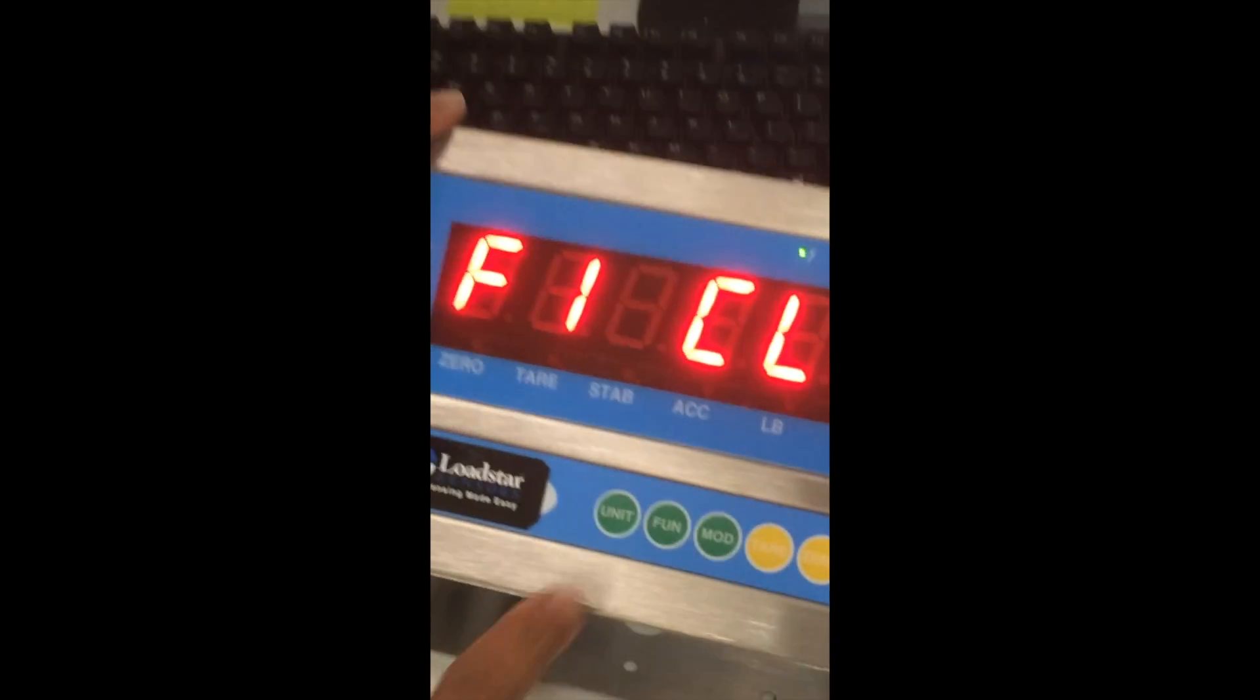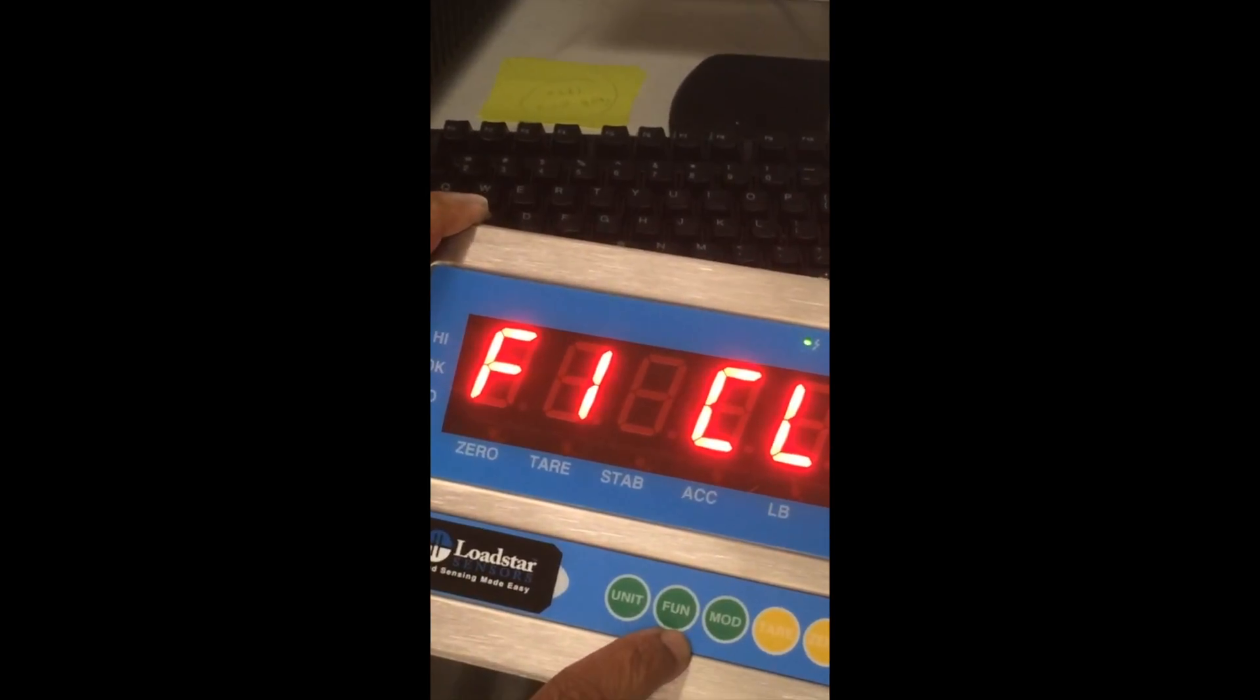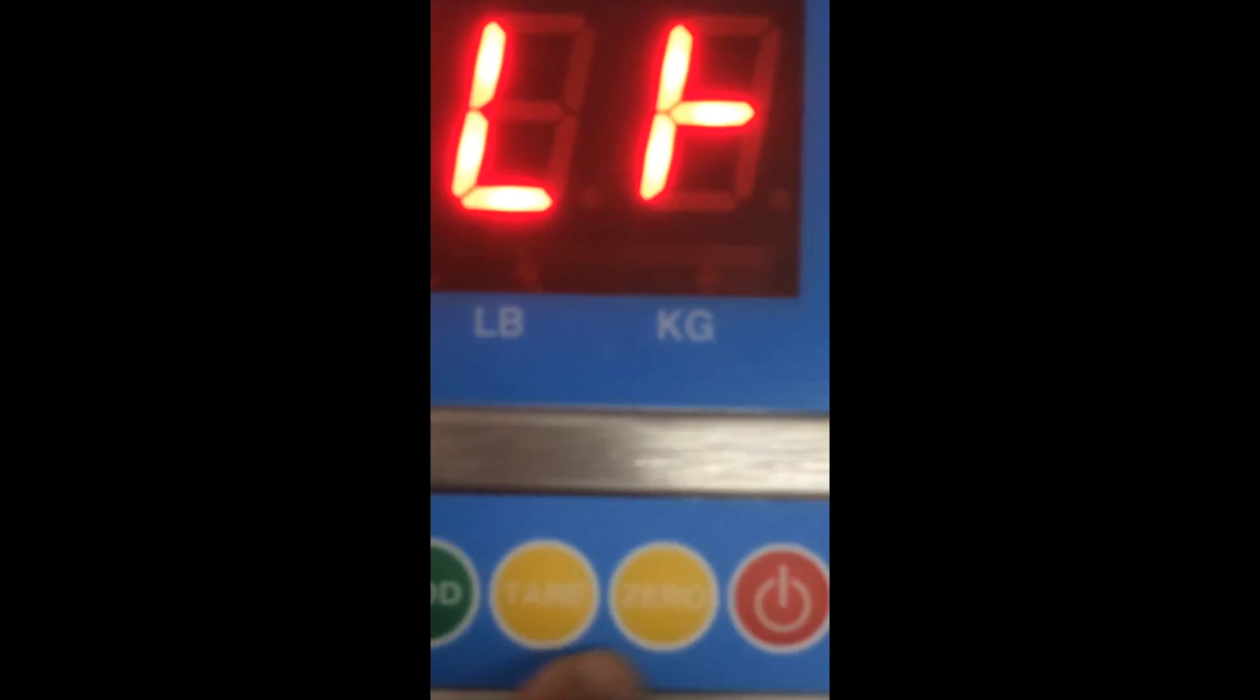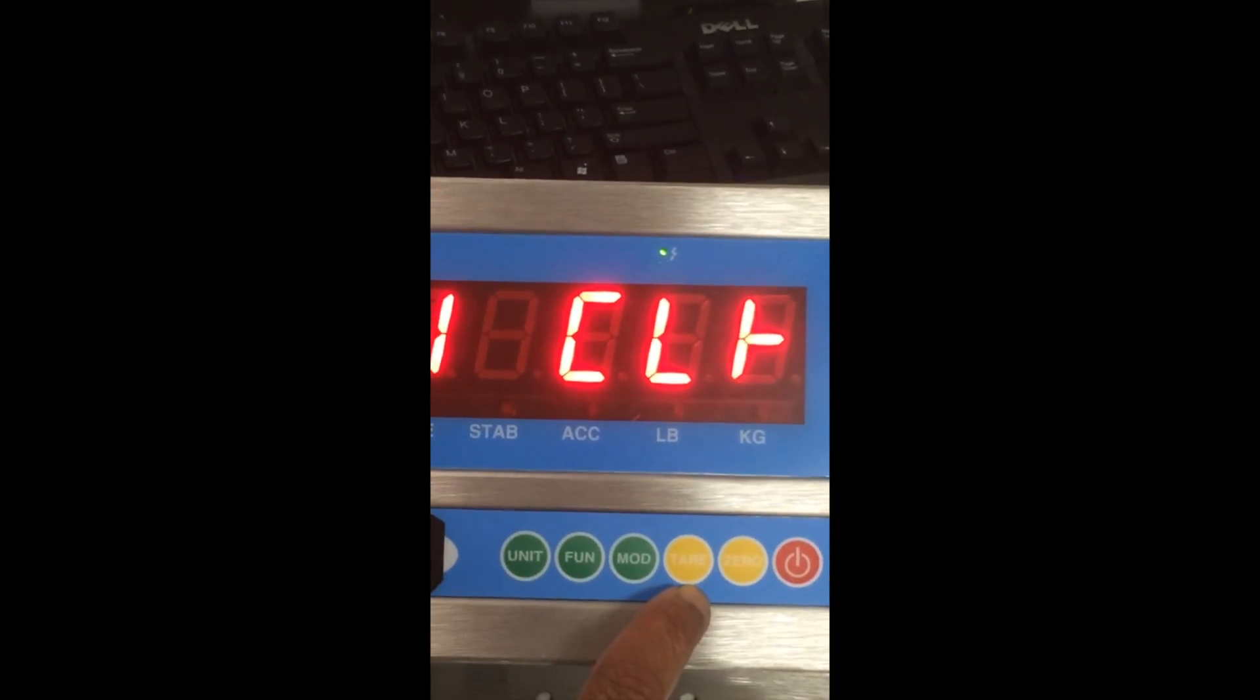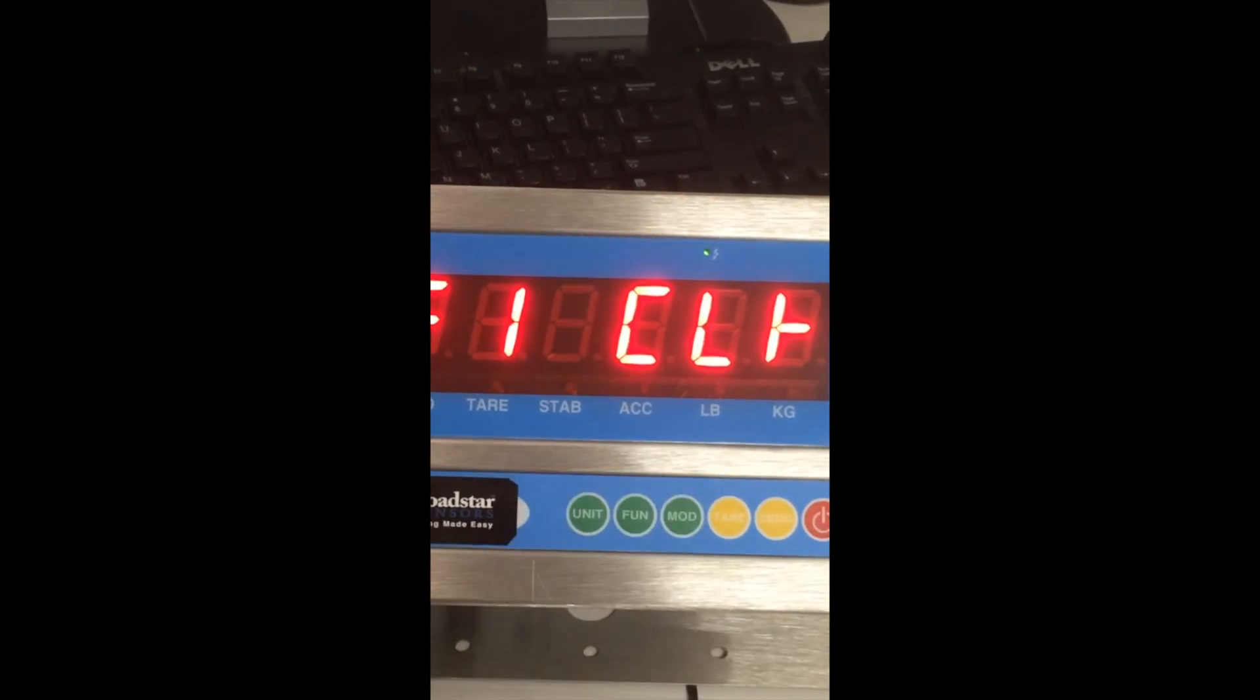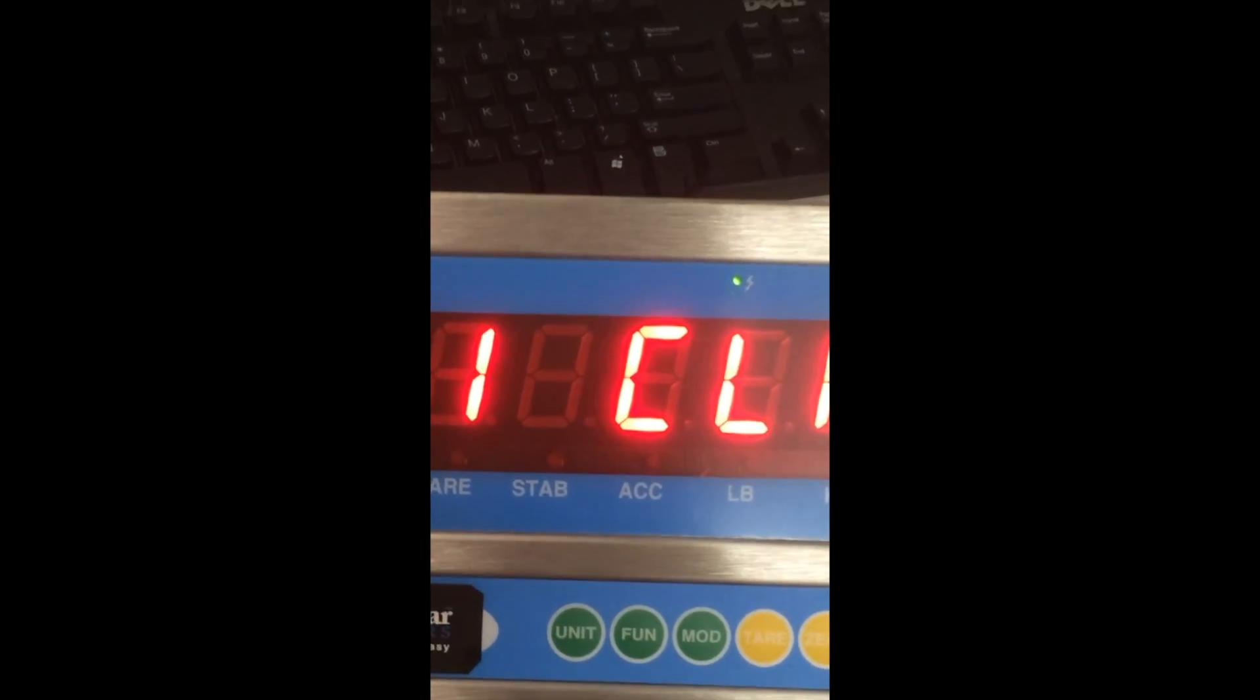Now you will see here the unit, there is a unit key, function F1 and mod key, tear and 0 and a power. During calibration procedure, the tare key acts like the up-down key in your computer and the 0 key acts like the left-right key in your computer and the function key acts like the enter key.